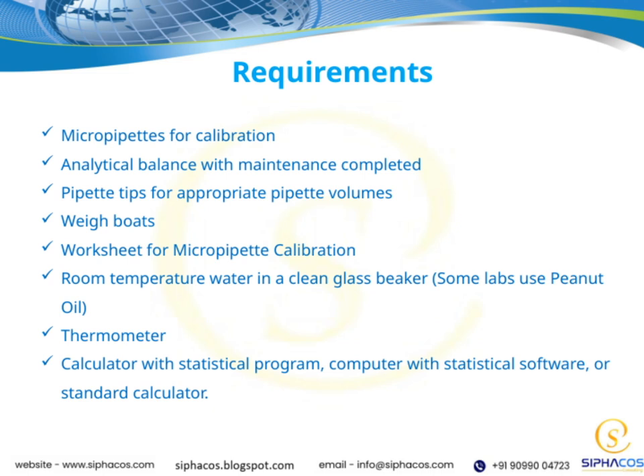First, you'll want your micropipettes ready for calibration, ensuring they are clean and in good working condition. An analytical balance with completed maintenance is crucial for precise measurements. Make sure your pipette tips are appropriate for the volumes you'll be measuring to ensure accuracy. Weigh boats are also necessary to hold the samples during weighing. You'll need a worksheet specifically for micropipette calibration to record your data systematically.